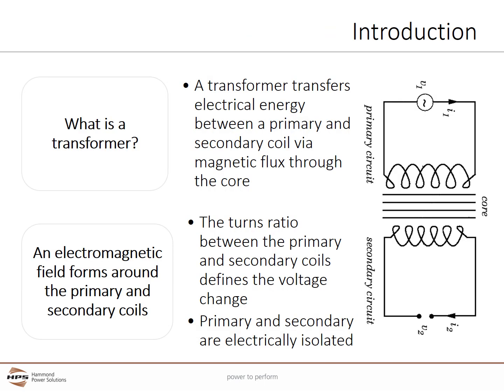A transformer is often used to change voltage. With drive isolation transformers, most configurations actually have the same input and output voltages, so the primary function is not to change voltage, but to provide electrical isolation between the primary and secondary coils.